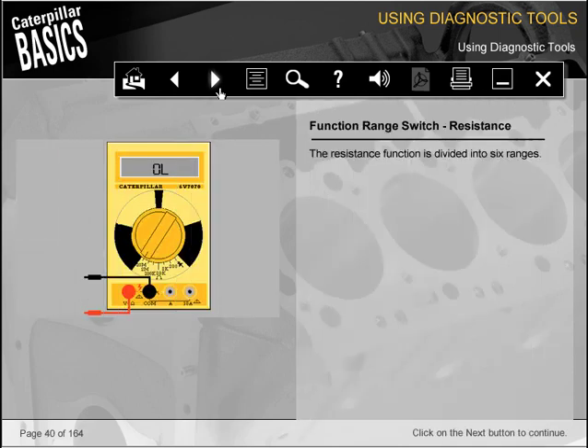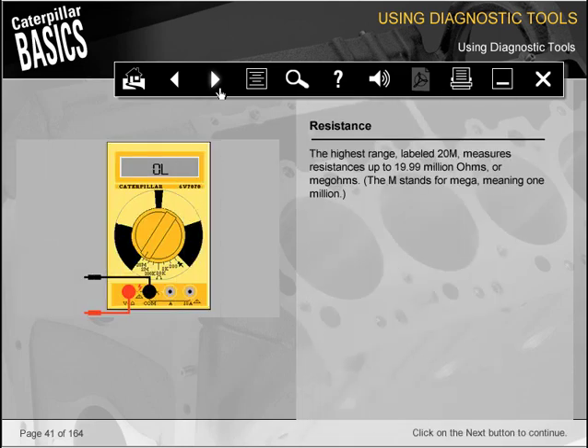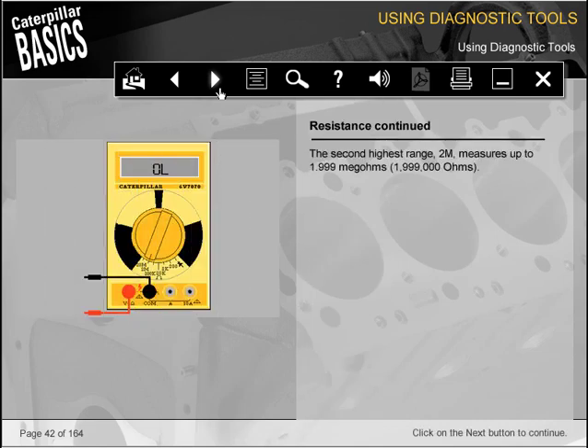The resistance function is divided into 6 ranges. The highest range, labeled 20M, measures resistances up to 19.99 million ohms, or megohms. The M stands for mega, meaning 1 million. The second highest range, 2M, measures up to 1.999 megohms, 1,999,000 ohms. The third range measures up to 199.9 thousand ohms, or kiloohms. Kilo means thousand, and so is labeled 200K.